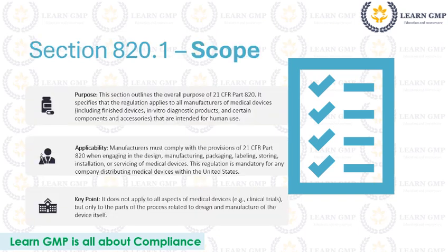Scope. Purpose. This section outlines the overall purpose of 21 CFR Part 820. It specifies that the regulation applies to all manufacturers of medical devices, including finished devices, in vitro diagnostic products, and certain components and accessories that are intended for human use.